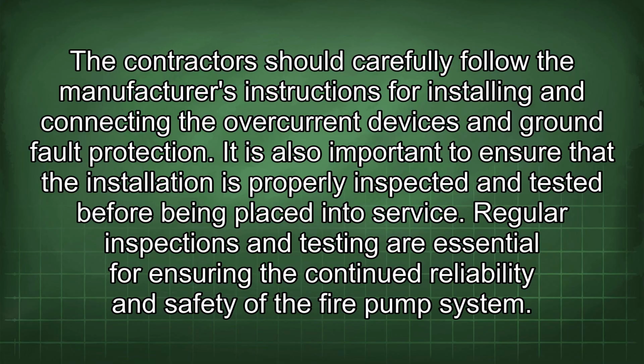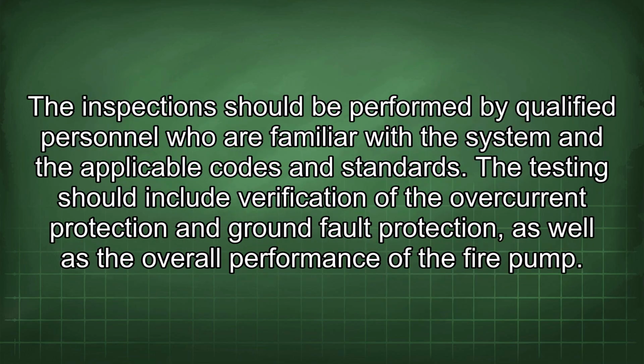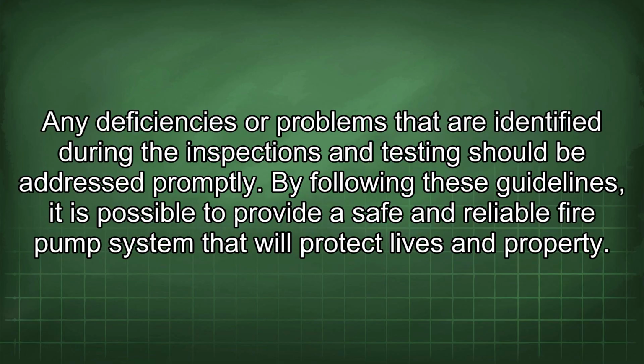Regular inspections and testing are essential for ensuring the continued reliability and safety of the fire pump system. The inspection should be performed by qualified personnel who are familiar with the system and the applicable codes and standards. The testing should include verification of the overcurrent protection and ground fault protection, as well as the overall performance of the fire pump. Any deficiencies or problems that are identified during the inspections and testing should be addressed promptly. By following these guidelines, it is possible to provide a safe and reliable fire pump system that will protect lives and property.